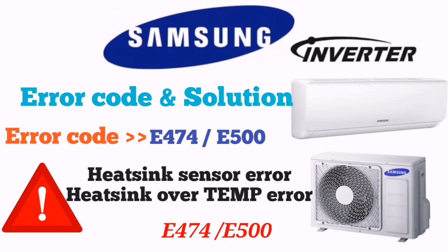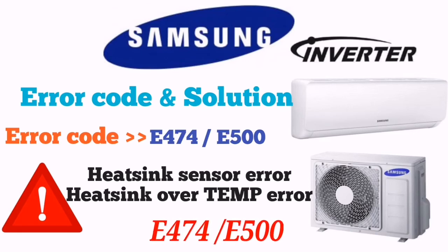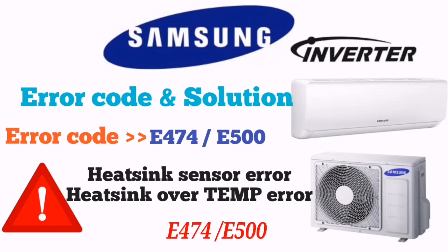When you see error E474, at that time your outdoor LED 1 will be blinking, LED 2 will be blinking, and LED 3 will be on. It means heatsink sensor error.